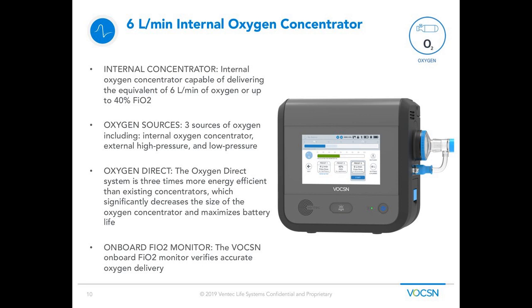That 6 liter per minute oxygen concentrator, again, in the same device using that same operating system, we have an onboard oxygen concentrator that can create up to 40% FiO2, the equivalent of 6 liters per minute. That's going to be pretty much all the oxygen that somebody needs outside of an acute care setting.